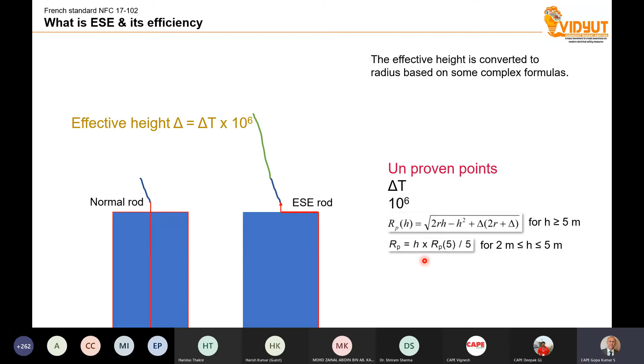Now, what do they do with respect to the testing? Delta T. How do they find out the delta T? Imagine you have a laboratory, and in the laboratory, first you test a single rod air terminal. That means a normal iron rod, maybe 1 meter in height, and at the top there is a plate. At the bottom there is again another plate. Between these two plates, a charge is created. Once the voltage goes beyond a certain limit, a breakdown happens. So they make a breakdown, and the time with which this particular device emits some kind of early streamers is taken, and this is called the time of the single rod air terminal.